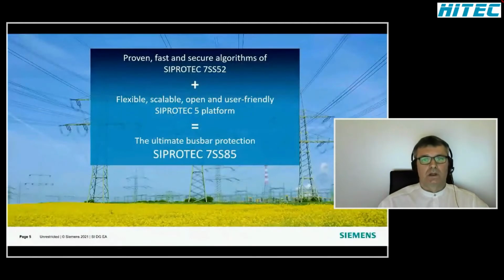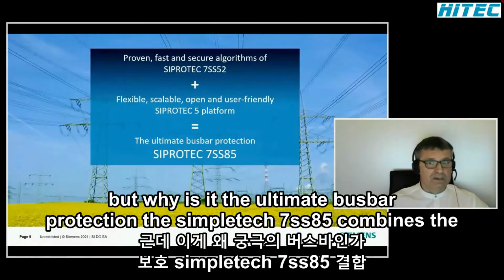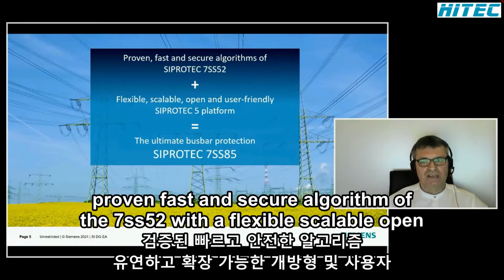With the release of SIPROTEC version 8.40 with a distributed busbar protection with up to 45 current measuring points, the SIPROTEC 5 busbar protection portfolio is completed now. We now have the ultimate busbar protection in our portfolio. But why is it the ultimate busbar protection?